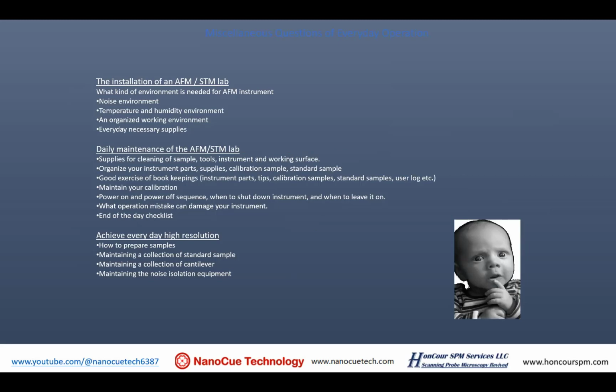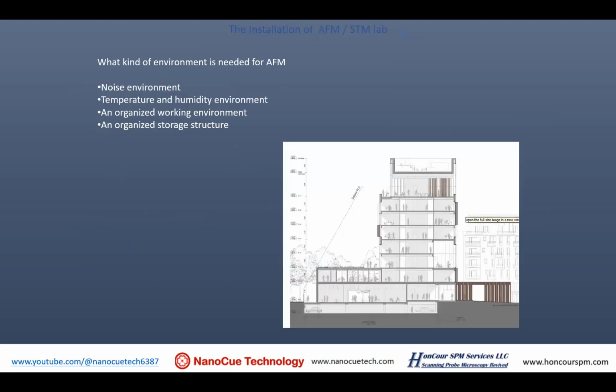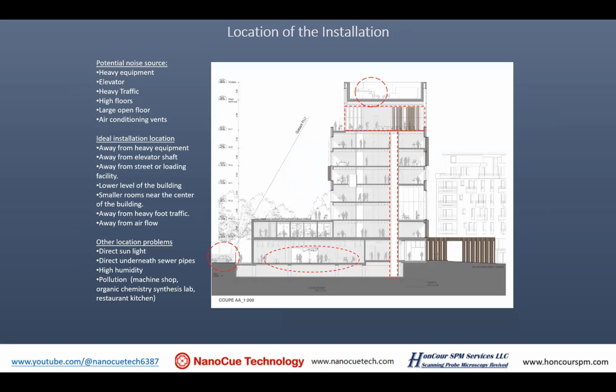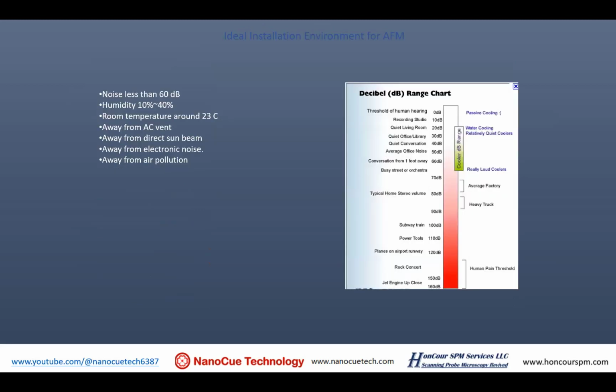This is the first one: when you have an instrument, how do you put it together? The instrument that I have supported, and a lot of other instruments, are normally installed in a building, and these university buildings could be of any kind, shape and size, in any location. There are certain places that normally have a lot of noise and instability that you should try to avoid. For example, when your lab is close to underground parking, or the lab has a very big floor, or it's close to elevators, machining and activities. These places typically have high noise levels. Try to avoid that.